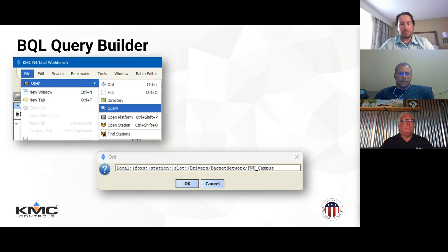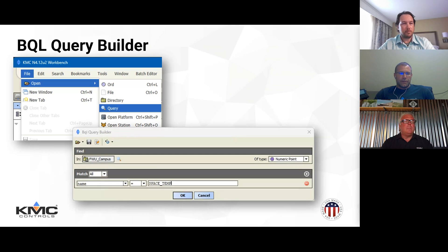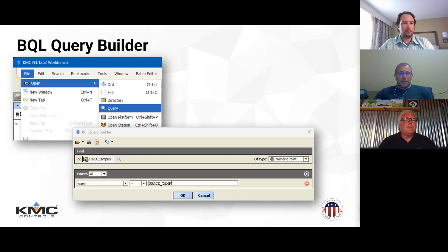Control-L will open a dialog and let you directly enter that BQL query as part of an ORD string. The BQL query itself determines the columns in the result table. It's really helpful - there's a little clock underneath the BQL query builder which shows your recent BQL queries. The BQL is based inside the station you're connected to, so when you run that query, it queries that station relative to it. If you use the clock and you're querying numeric points, you connect to another station and just rerun that same query and it'll be there for you.